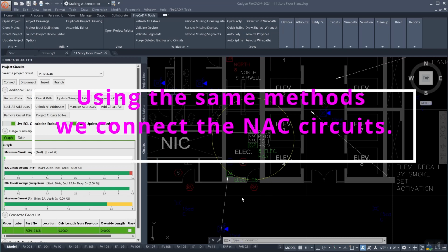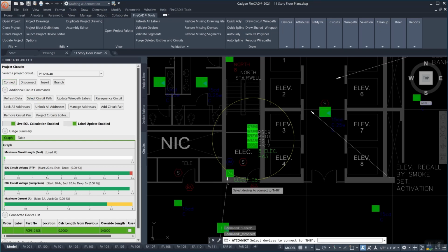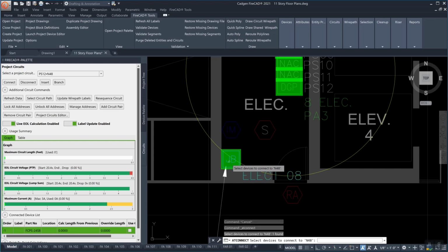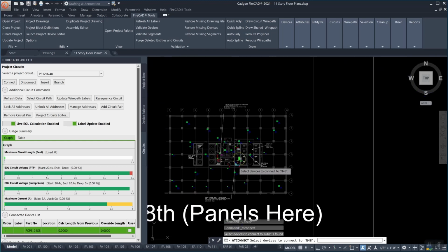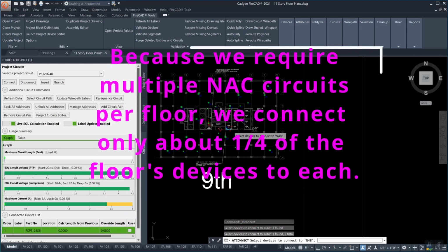Now, using the same methods, we connect the NAC circuits. In this case, starting from a NAC panel on the 8th floor, we follow the junction boxes up to the 11th floor.